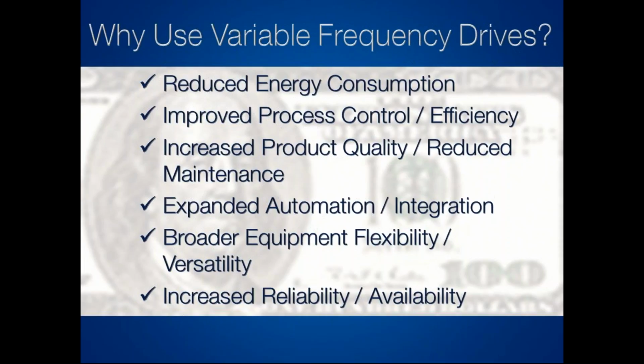So let's say you have, for whatever reason, a 20 horsepower drive sitting on your shelf left over from another job. That 20 horsepower drive can be used on any motor 20 horsepower and below. So all you do is take that 20 horsepower drive and set it for your 5 horsepower motor that you need to be running it on. So you've got a lot more flexibility with your drives. And then as the years have gone on, drives have just become much more reliable, much more affordable, and much more available to you guys. So in a lot of cases, a drive is going to be a much better option than a starter. Go ahead and go to the next slide.